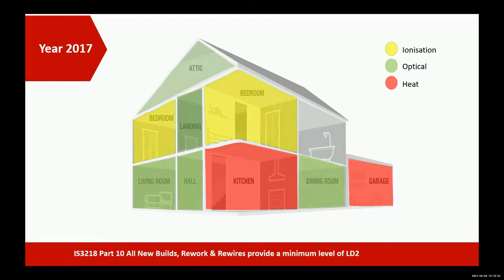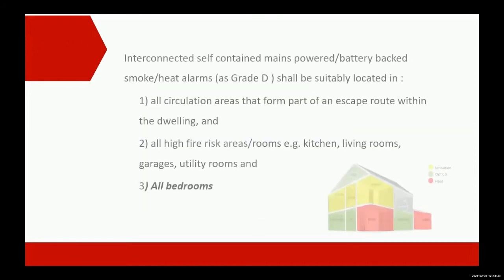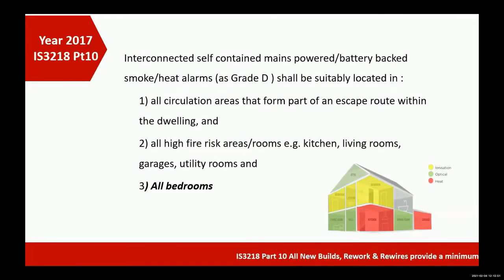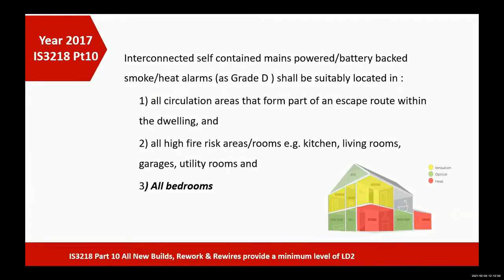The next review that came was in 2017. And at that stage, we could now reference the IS 3218 standard, Part 10, which was the first time this was available, because prior to that, in 2006, the IS 3218 standard wasn't available. So when you look at this in relation to the way the standard has moved from 2006 to 2017, we look at the installation, and you can see from the graphic there that there's a high density of smoke detection and heat detection within the premises itself. So what they look for at that stage is interconnected self-contained mains-powered battery backup, smoke and heat alarms as per grade D. And they're to be located in all circulation areas that form part of an escape route within the dwelling, and in all high-risk areas and rooms, for example, kitchen, living rooms, garages, utility rooms, and all bedrooms.